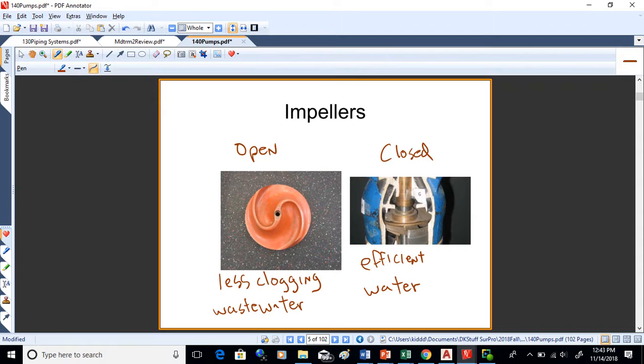Closed impellers might be around 80-90 percent efficient, or 80 percent or higher. Open impellers may be down around 50 percent. You really pay the price on an open impeller, but you need to have them on a wastewater pump.